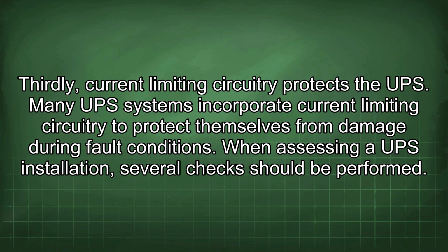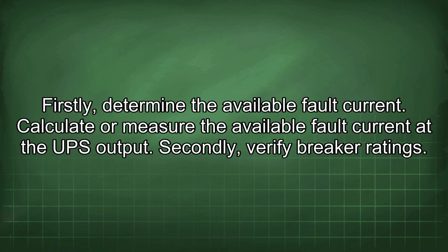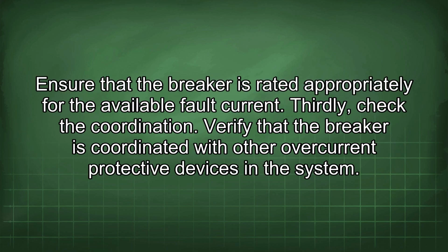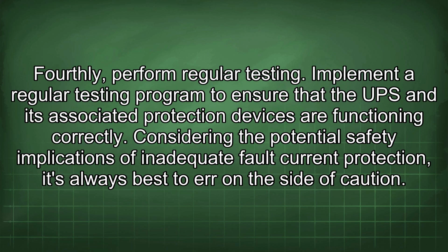When assessing a UPS installation, several checks should be performed. Firstly, determine the available fault current. Calculate or measure the available fault current at the UPS output. Secondly, verify breaker ratings. Ensure that the breaker is rated appropriately for the available fault current. Thirdly, check the coordination. Verify that the breaker is coordinated with other overcurrent protective devices in the system. Fourthly, perform regular testing.